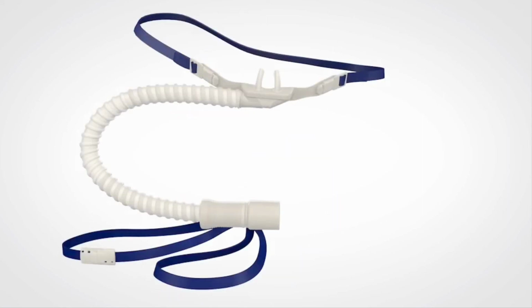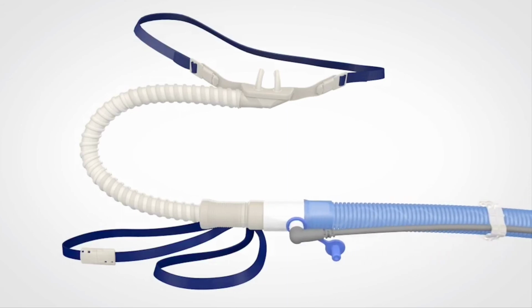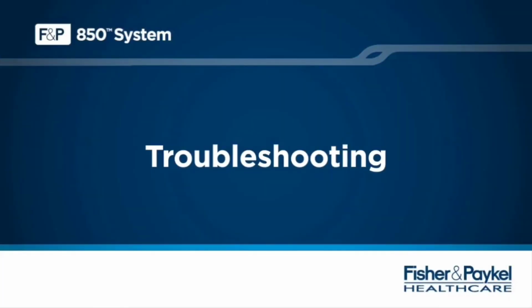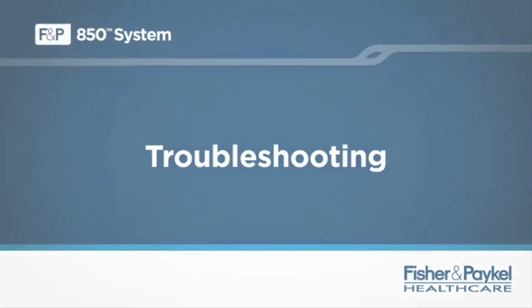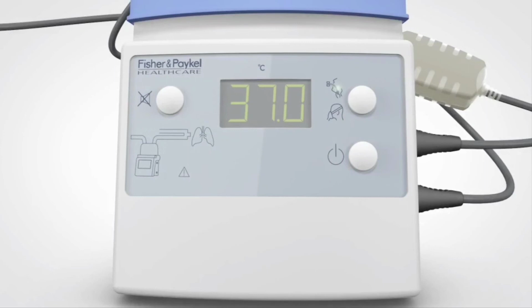Fit the Optiflow nasal cannula to the patient according to the instructions provided with the cannula. Connect the Optiflow nasal cannula to the end of the inspiratory limb and adjust the lanyard to take the weight of the breathing circuit. In this section, we'll look at common setup warnings and operational alarms. The MR850 uses a simple drawing to indicate alarm conditions.